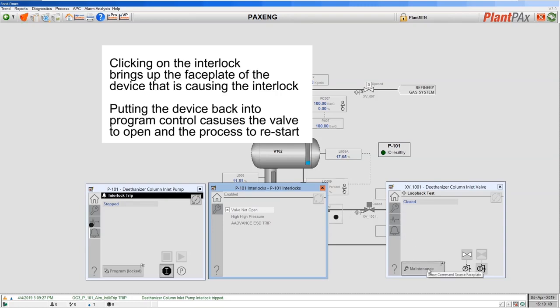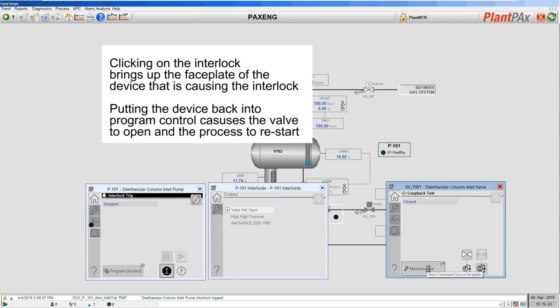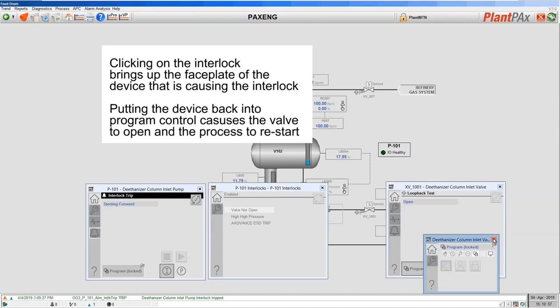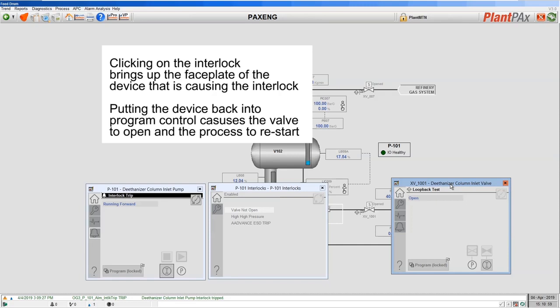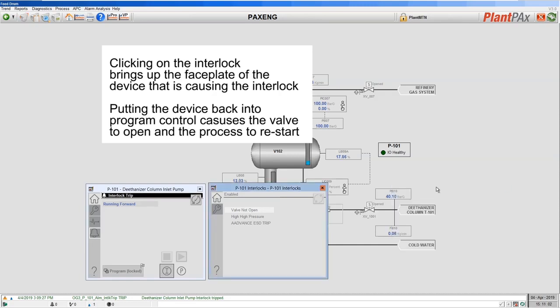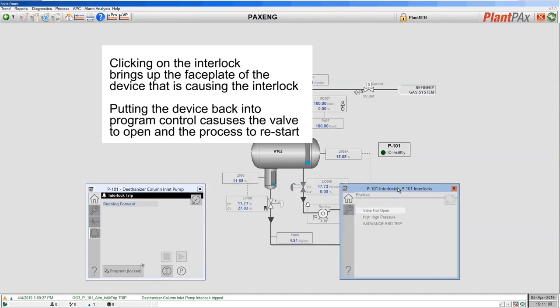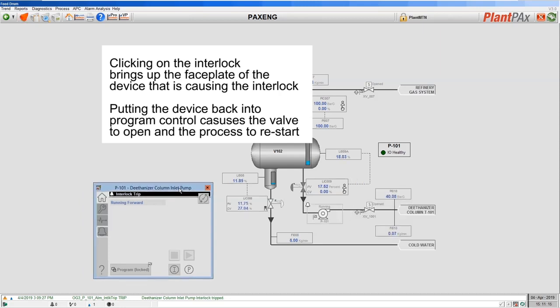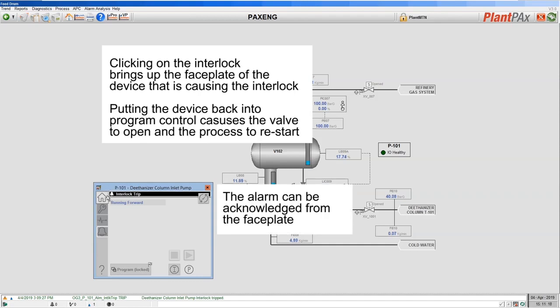The quickest way of doing this is to put the valve back into program mode by removing the maintenance override. I bring up the faceplate again and release the maintenance request. As soon as I do that the device goes back into program mode and my controller opens the valve. Because the interlock is not latched, as soon as the valve opens the pump starts again. I can close the interlock faceplate and see that my pump is running, and from the main faceplate I can see that there was an interlock trip in the past, which I can acknowledge to remove that interlock alarm — and everything's back to normal.